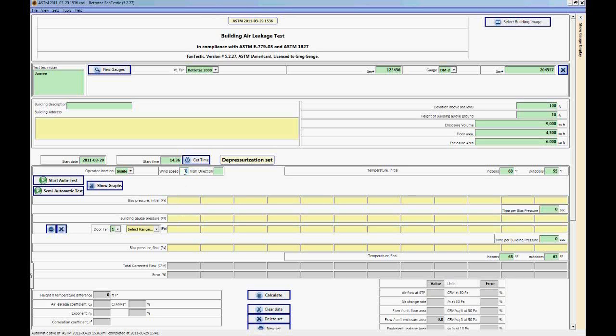So let's say we have actually done a pressurization test. We're going to want to write down the wind speed. The wind speed has to do with one of the deviation statements for ASTM. If it's above 4 miles per hour the test is no longer valid. So let's say it's 1 mile per hour coming from the west.